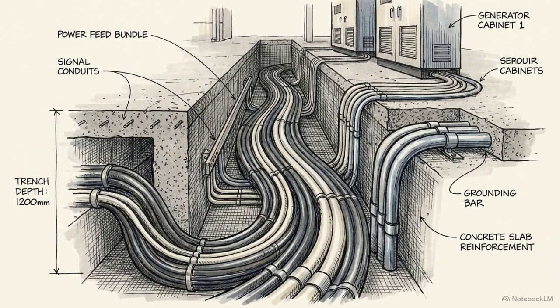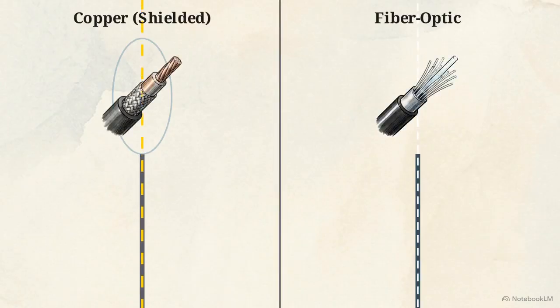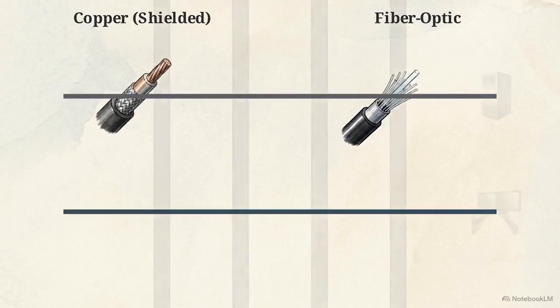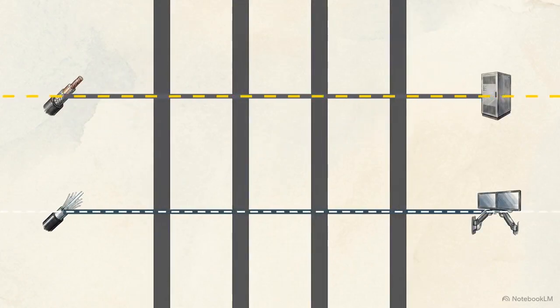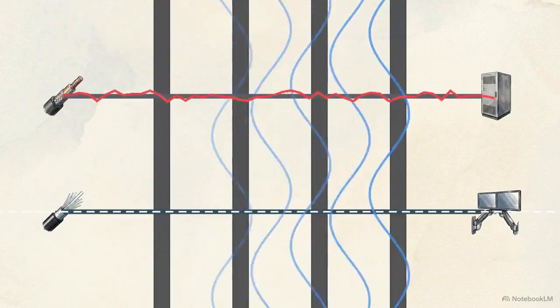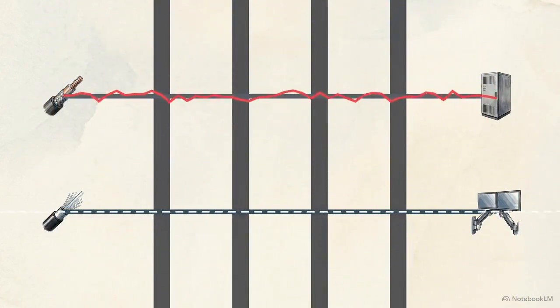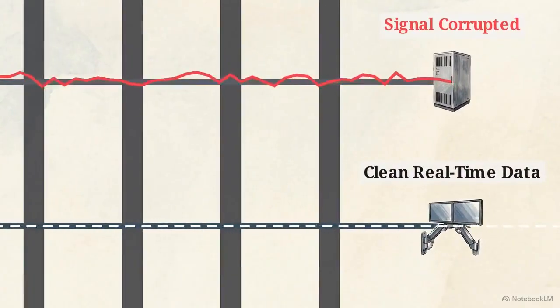and control consoles. This diagram compares data pathways. Standard copper wiring is insufficient. Fiber optic cables are mandatory to handle massive real-time imaging data. Crucially, fiber optics don't absorb electromagnetic interference. This is a strict requirement in hybrid suites, where heavy MRI magnetic fields would otherwise corrupt the signal.